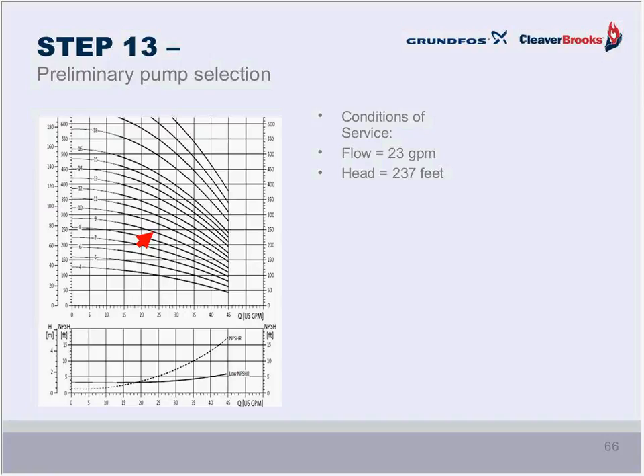Now, in the previous exercise, we used a variable speed pump also when we were operating against a feed valve. And in that situation, we had significant energy savings. And with this exercise's variable speed pump, we're going to experience similar energy consumption reductions at those lower flows. So once again, we have that benefit. At lower flows, lower power consumption. And you need to run a load profile on your anticipated boiler operation to determine just exactly how that load profile can be translated into energy savings.